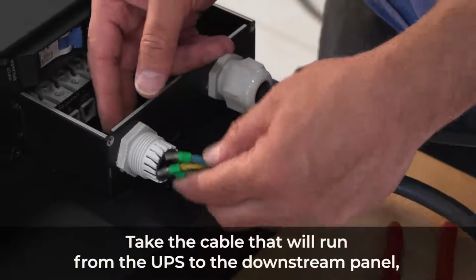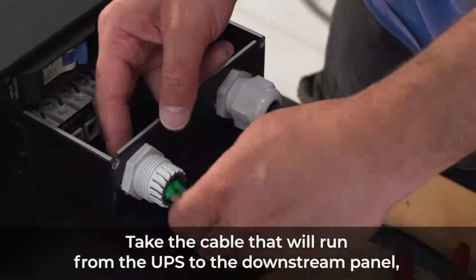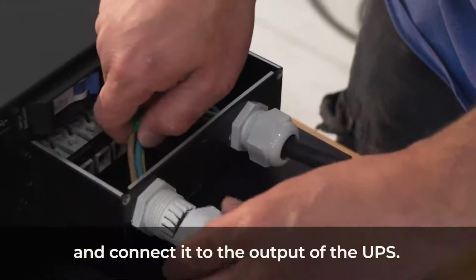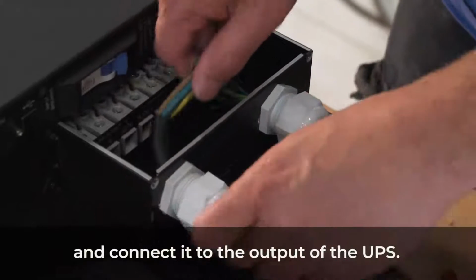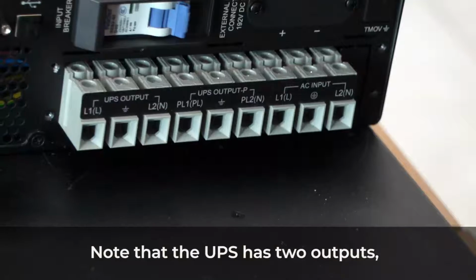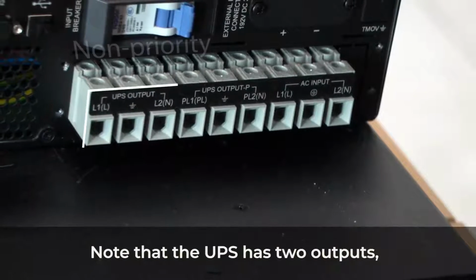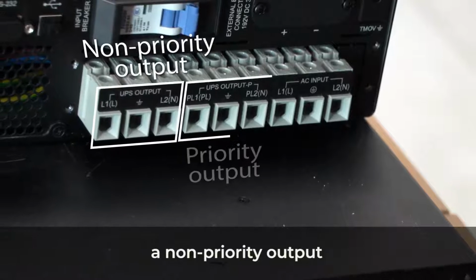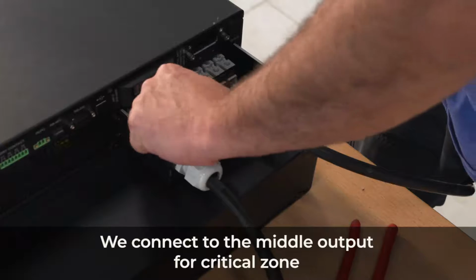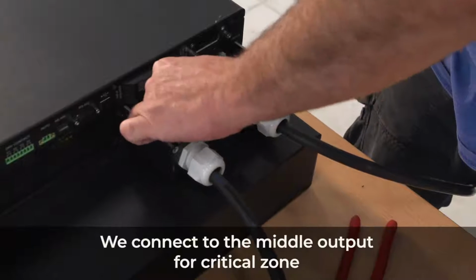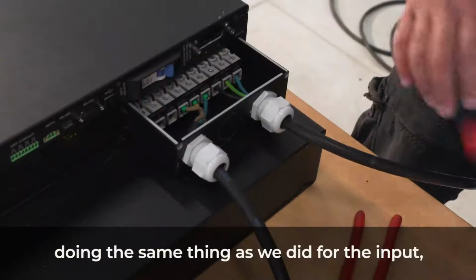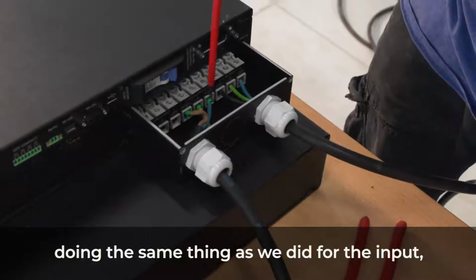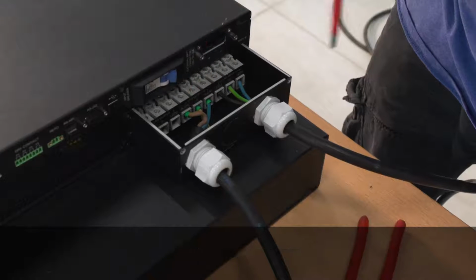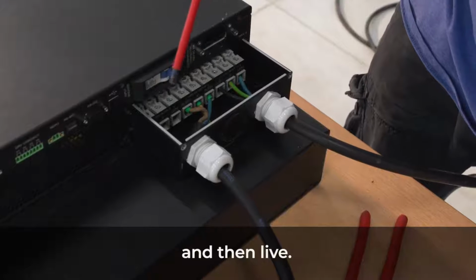Take the cable that will run from the UPS to the downstream panel and connect it to the output of the UPS. Note that the UPS has two outputs, a non-priority output and a priority output. We connect to the middle output for critical zone, doing the same thing as we did for the input, starting with the earth, then the neutral, and then live.